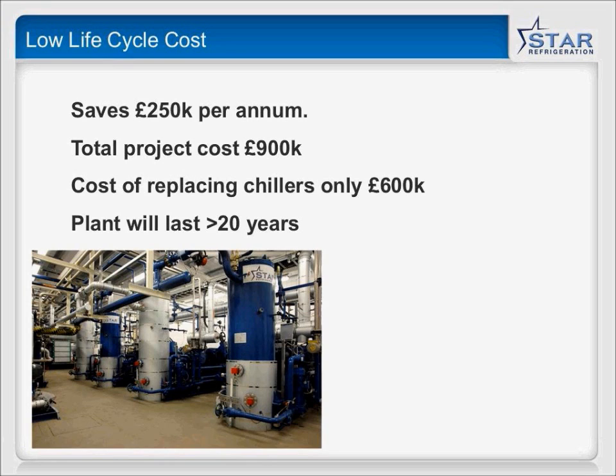The boiler will typically be about 85% efficient. So you're consuming 1125 kilowatts of heating energy and 200 kilowatts of electrical energy to achieve 600 kilowatts of cooling energy. What if, instead of throwing that heat away, we could capture it?